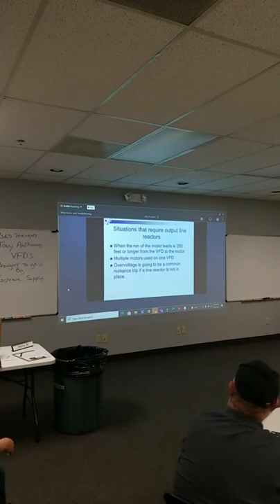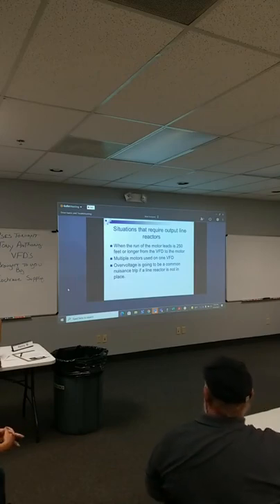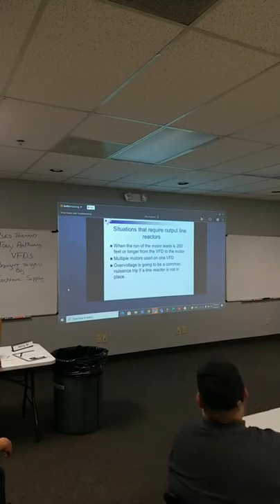So Marathon is a motor I know they were one of the best on the market as far as the quality of insulation they put in. They say their motors can handle several hundred feet, off the record of course, without putting any kind of protection on it. A cheaper motor, you get to 100 foot and you may have issues. So really it depends on the motor. But the rule of thumb is, if the motor and the wire run is a couple hundred foot from the drive, we need to talk about doing something to protect that motor from what we call dV/dt, which is those high pulses of the DC that we're pulsing out to the motor.